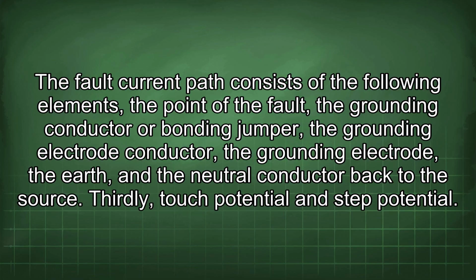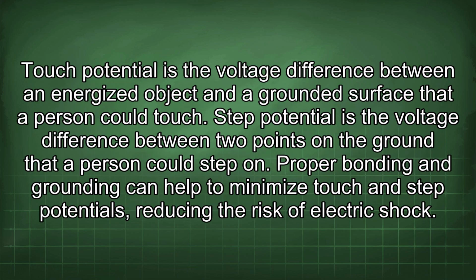source. Thirdly, touch potential and step potential. Touch potential is the voltage difference between an energized object and a grounded surface that a person could touch. Step potential is the voltage difference between 2 points on the ground that a person could step on. Proper bonding and grounding can help to minimize touch and step potentials, reducing the risk of electric shock.